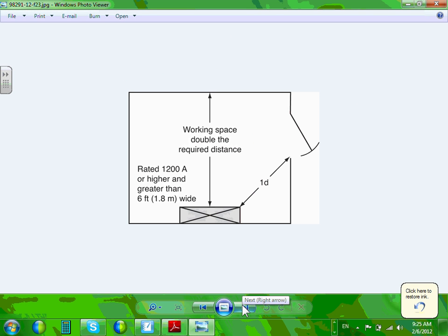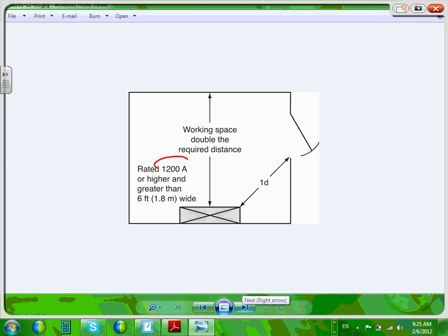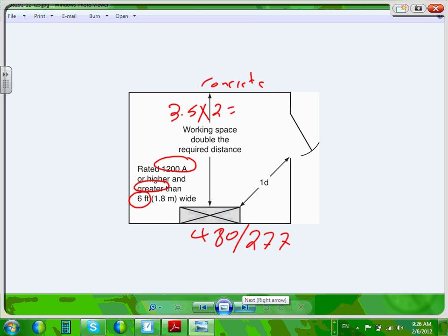Okay, here's what I talked about, guys, doubling the equipment distance. This is 1200 amp or higher, and greater than 6 feet. Working space double. Suppose this is 480/277, and suppose that wall was concrete. If you go to concrete, grounded, that will give you 3.5, right? So the clearance should be 3.5, but because we're going to double it, times 2, that will give you what? 7 feet. So if the architects give you 7 feet in front of the equipment, that's how to negotiate with the architect. 7 feet in front of the equipment, then you can get away with one entrance.